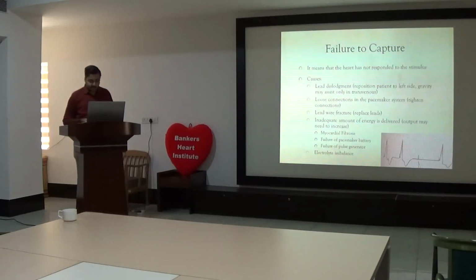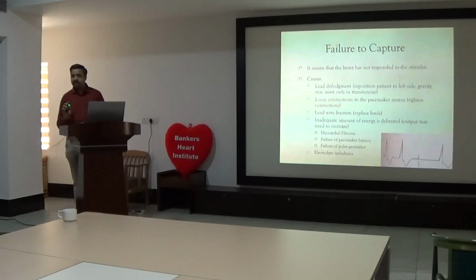But yes, the book says it may work. Loose connection: either the connection of the lead with the pacemaker is loose, or the connection inside the patient is loose, that is, the lead is dislodged. So at any point, there may be a loose connection of the pacing lead with the pacemaker. Lead wire fracture: in that case, the corrective measure is replacement of the wire.